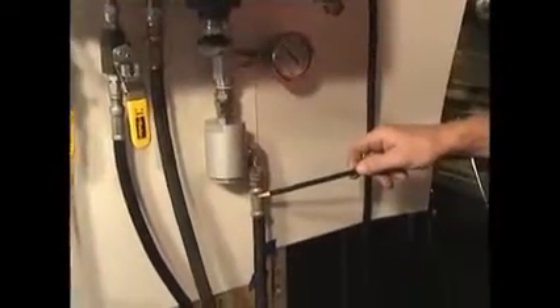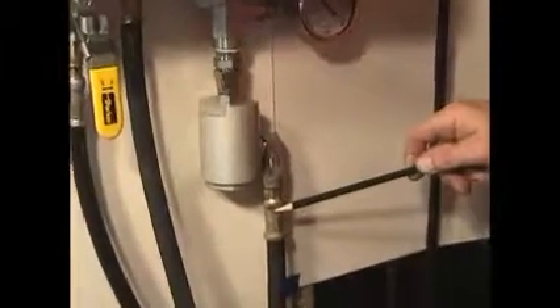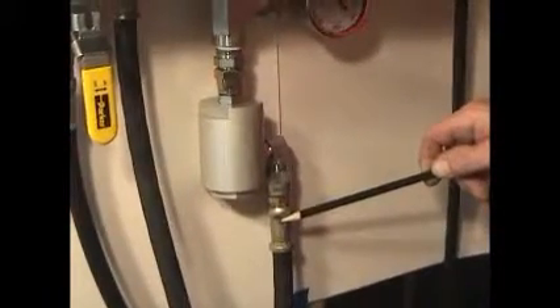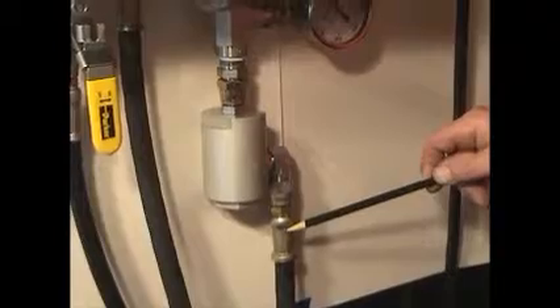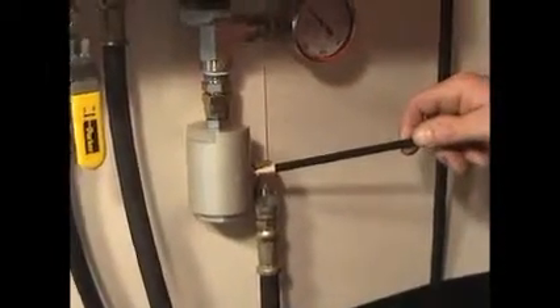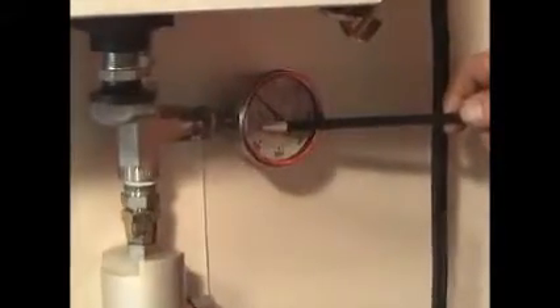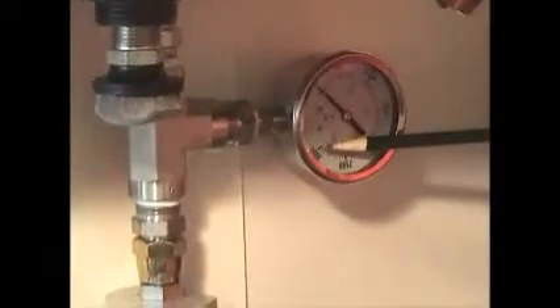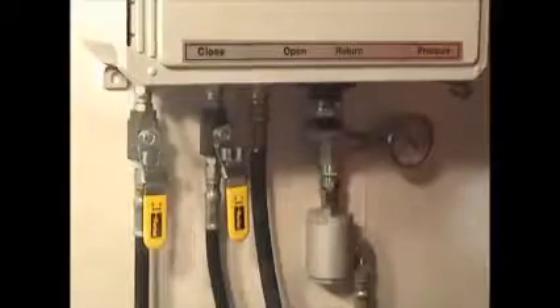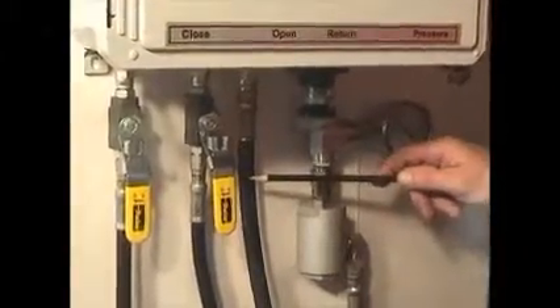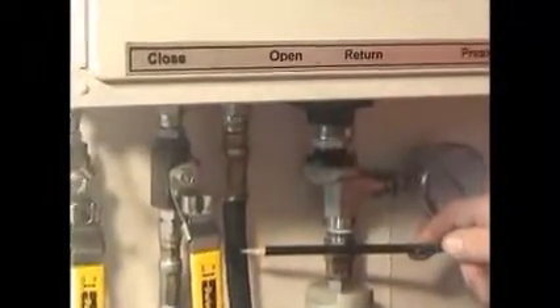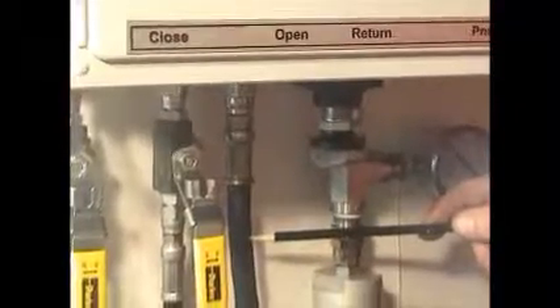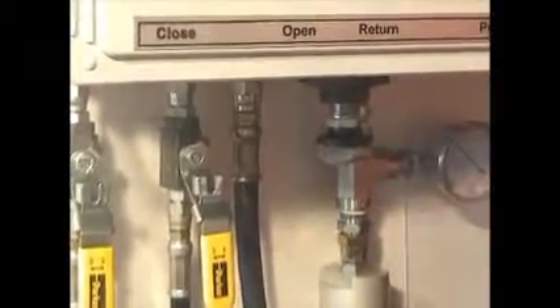The far right-hand hose is a pressure hose coming from the pressure port of the hydraulic pump. This hose is attached to a high-pressure filter. Next is the pressure gauge used to monitor the main pressure coming from the pump. The second hose from the right is a hydraulic return line. This hose directs oil back to the hydraulic oil reservoir.